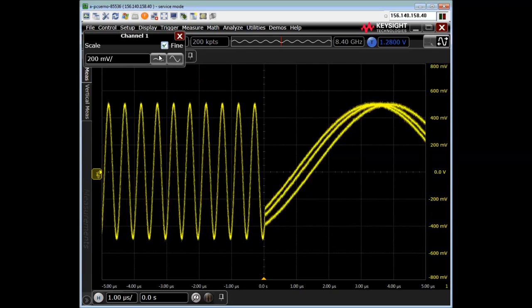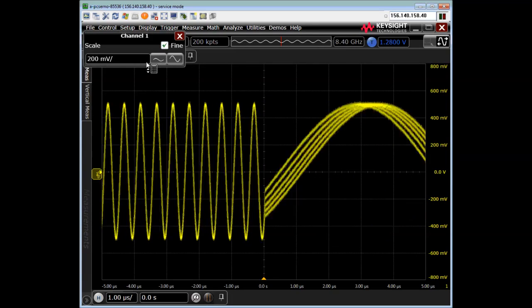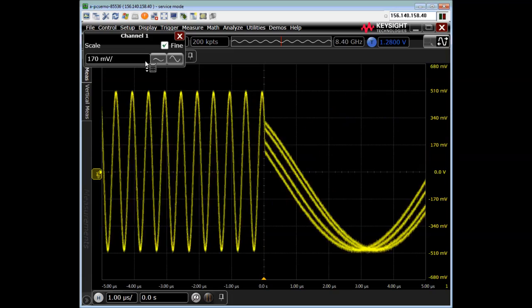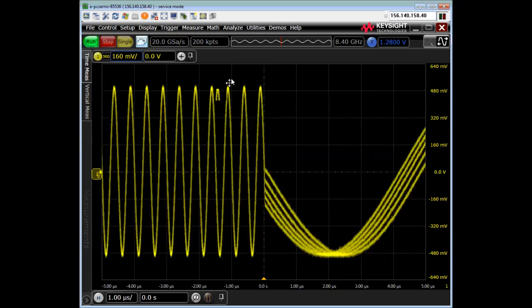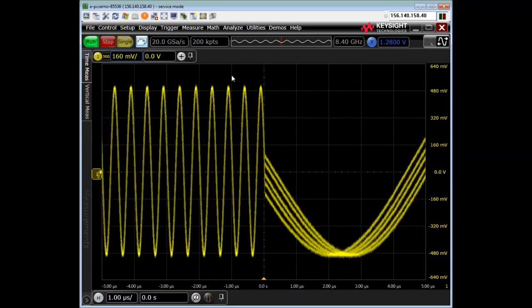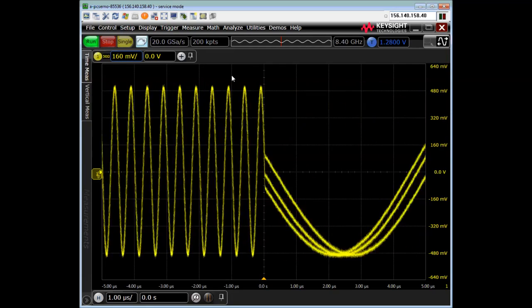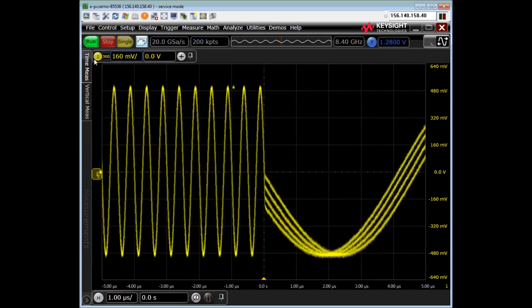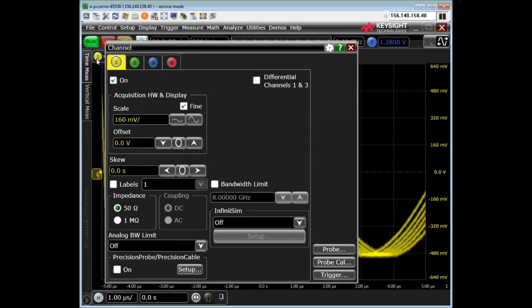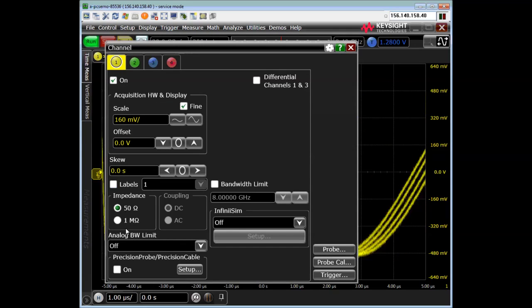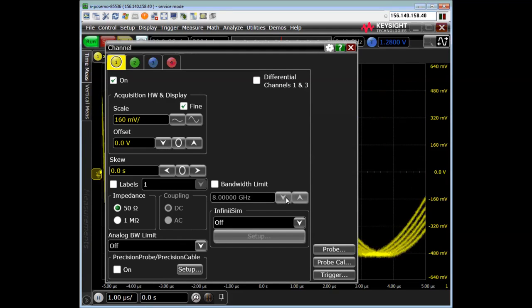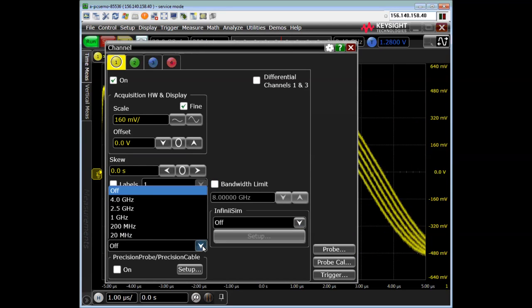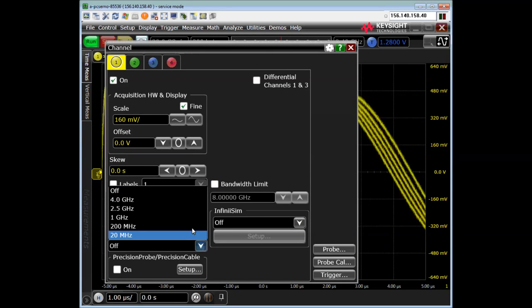Really, I want to use about 7.2 divisions, which optimizes the signal-to-noise ratio. And since this is a 2 megahertz max sine wave, I can also turn on an analog bandwidth limit.